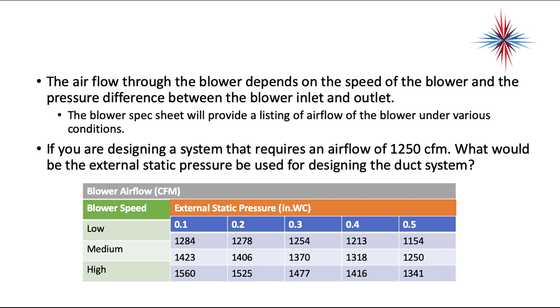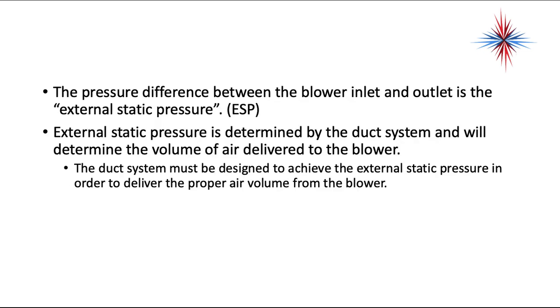A 0.5 inch water column is a standard for maximum external static pressure, but it's very important to check the blower spec sheets — this is just an example. The pressure difference between the blower inlet and outlet is the external static pressure. External static pressure is determined by the duct system and determines the volume of air delivered. The duct system must be properly designed to achieve the correct external static pressure in order to deliver the proper air volume.